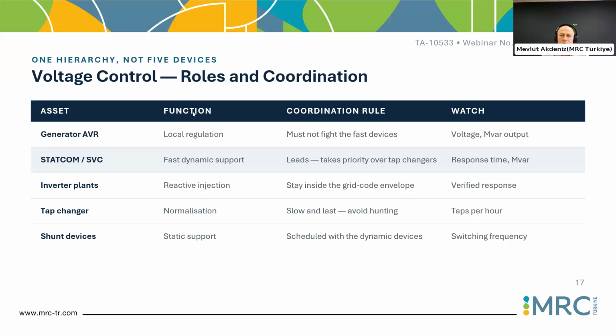Tap changers, similar to transformers, can regulate the voltage with a slow response. These are switches. They can regulate the voltage and reactive power flow also in a couple of 10 seconds, but it should be well coordinated with the real-time operation of SVC and STATCOM. So the optimum reactive power flow solution should be implemented with these different time response machines.